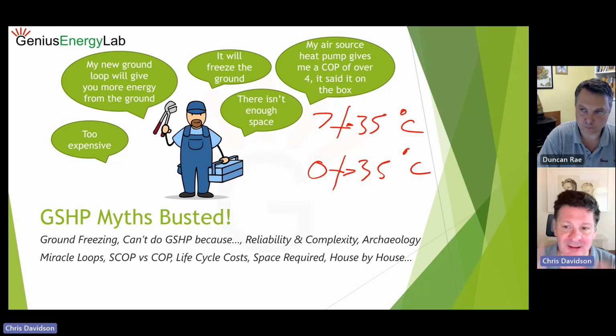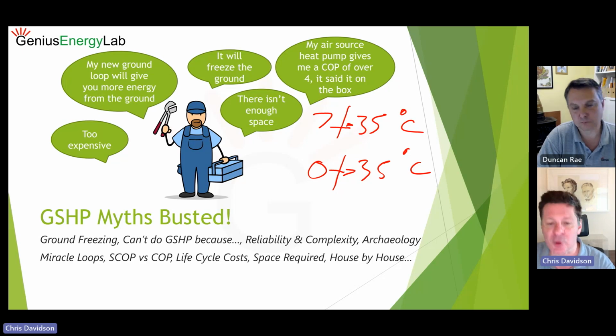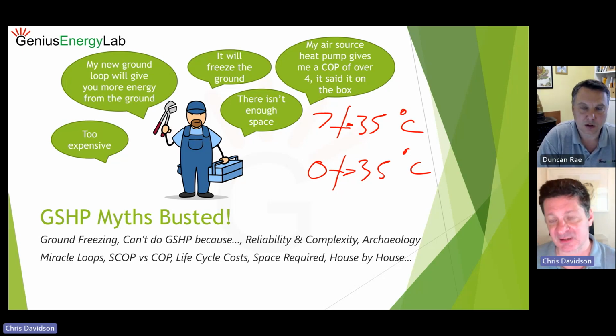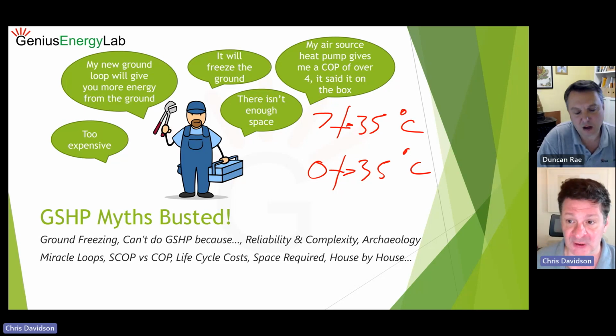But when you start to look at life cycle costs on the system, and I'll come back to that in a second, ground loops as an asset, then you start to really come in favour of ground source. So if that initial cost or purchase cost is the only consideration, then probably air source is the best solution. But if you've got any view on life cycle cost, then ground source is going to be a significantly less expensive whole life cost of ownership.